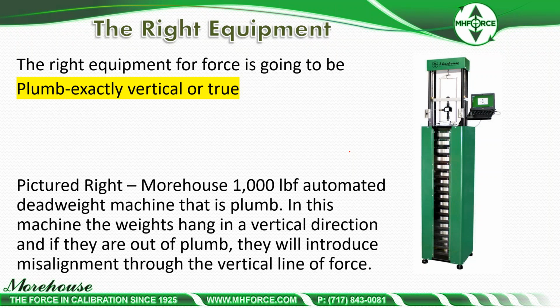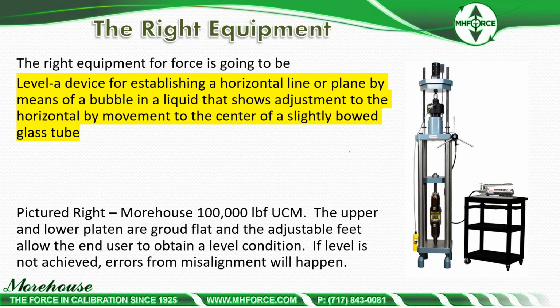Here, plumb means exactly true or vertical. A picture of our dead weight machine, a 100,000 or 1,000-pound automated dead weight machine that is plumb. Weights hang in a vertical direction, and if they are out of plumb, they will introduce misalignment through the vertical line of force. In newer machines, we're also stacking weights heaviest on top. That reduces the pendulum effect of the weight swing. So newer machines, with heavier weights on top, are much more plumb, rigid, square, and free of torsion.